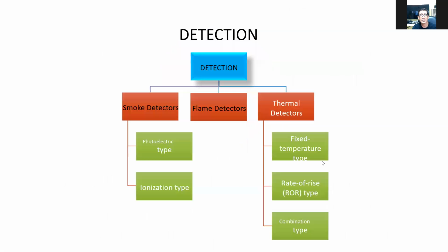Okay, so we have this detection. In case of detection, we have the smoke detectors, the flame detectors, or the thermal detectors. Smoke detectors come in the photoelectric type and the ionization type. Thermal detectors come in the fixed temperature type, the rate of rise (ROR) type, or a combination of the fixed and rate of rise types. These are the different types of equipment that you can use for detection of possible fire by flame, smoke or heat.